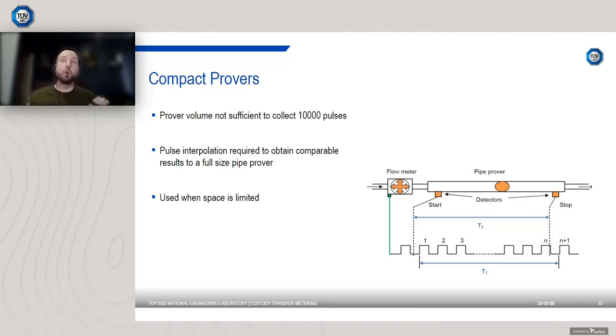Well, these are termed compact or small volume provers. Now, to get the resolution required to obtain similar uncertainty to a conventional prover, you need to utilize pulse interpolation. So you need to calculate those fractional pulses. Now, a really common technique is dual chronometry, and this uses two timers. So the first timer times the interval between the detector switches, and the second timer times the interval between the nearest integer of meter pulses. So the first pulse after the start switch and the first whole pulse after the stop switch. By using a ratio of these times, you can work out an interpolated pulse count.